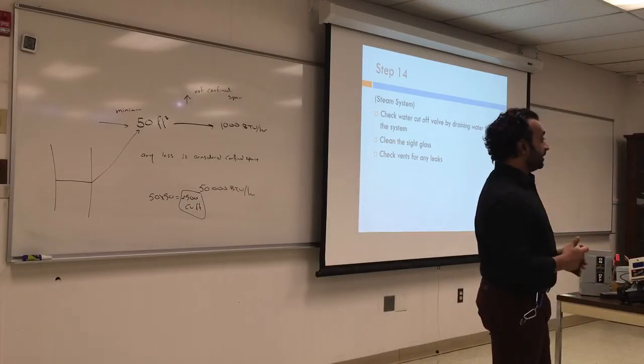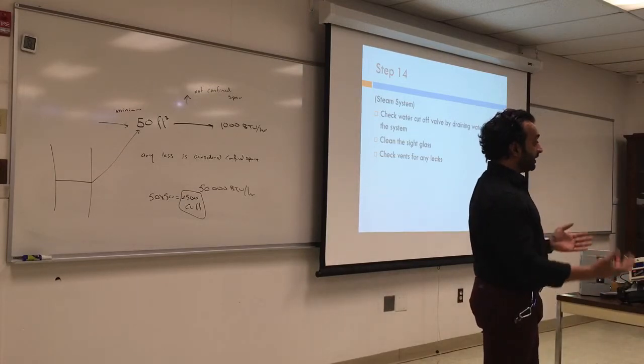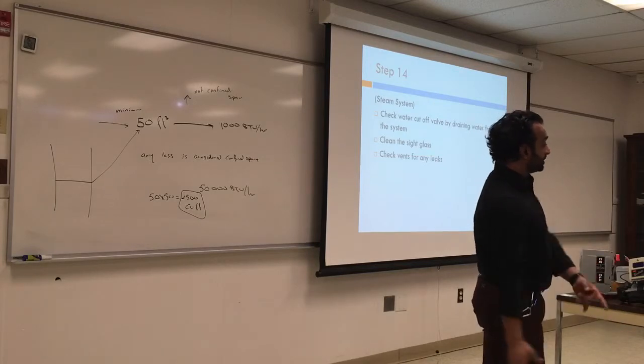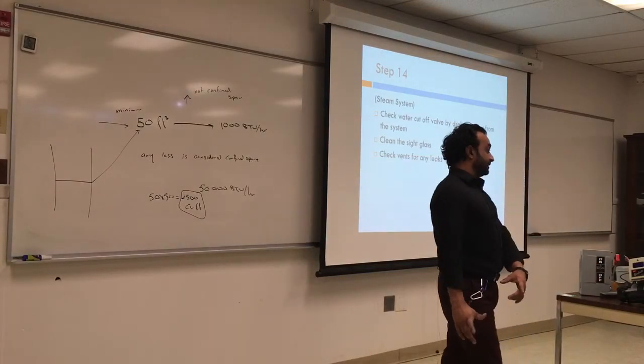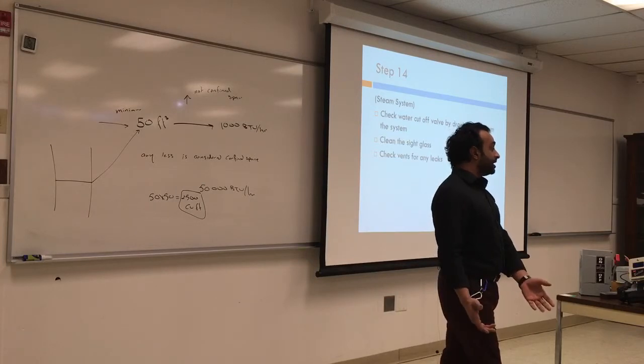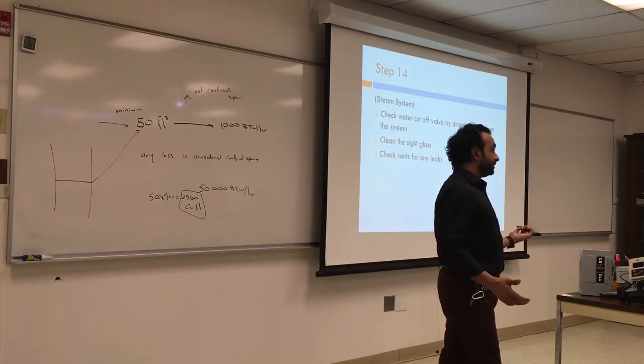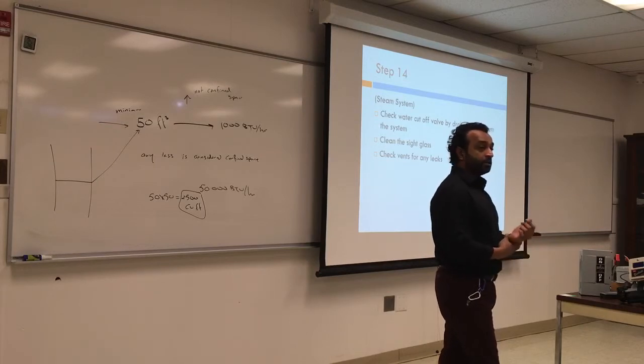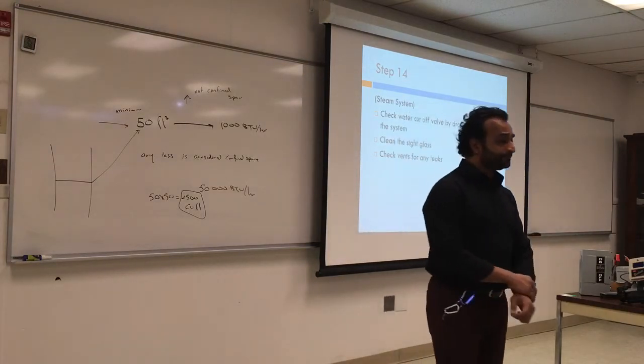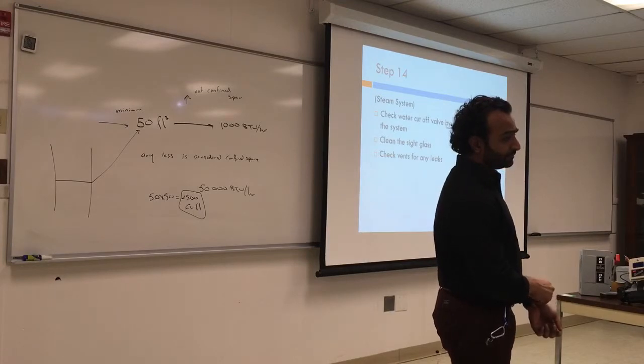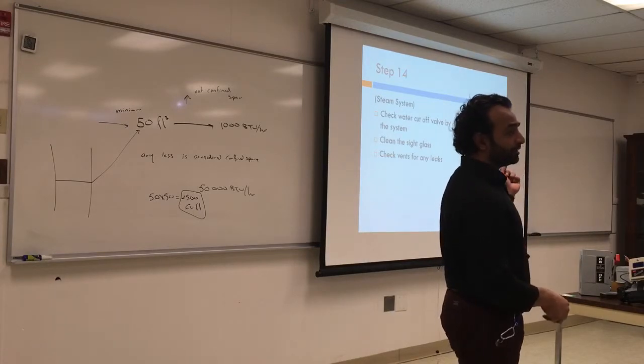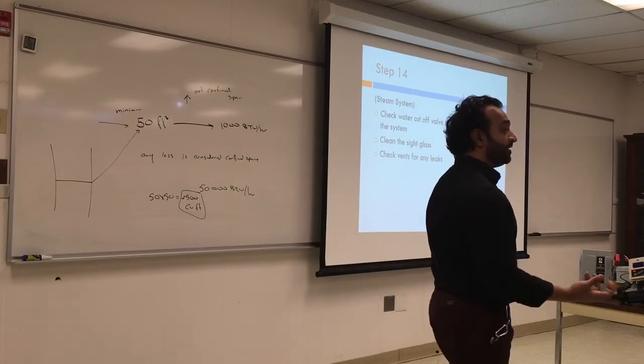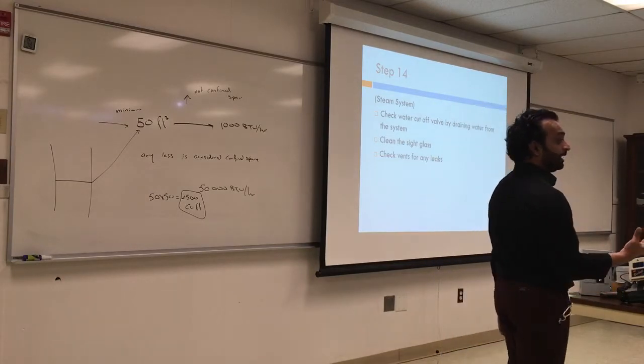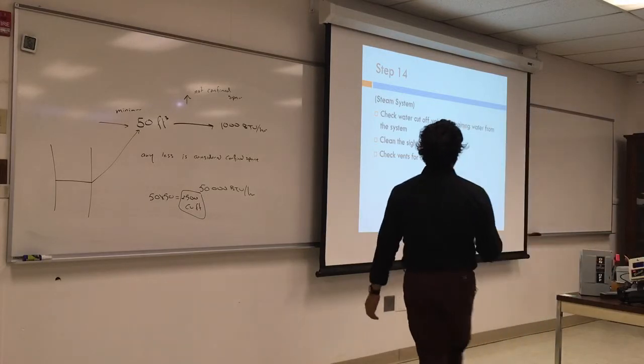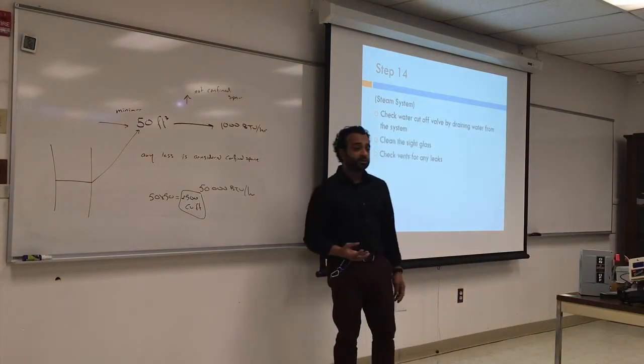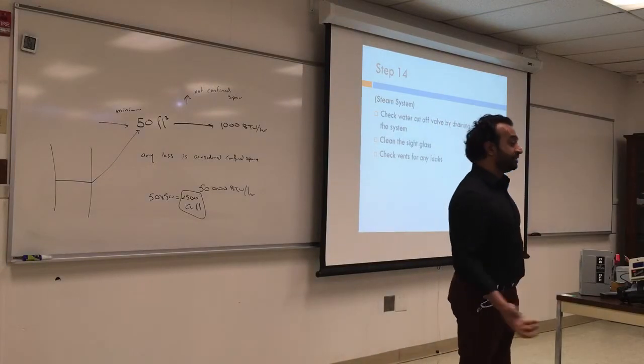Drain where? Every steam boiler has a drain at the bottom. Usually there's a hose and there's a small drain in the basement. It's not that big a bucket. It shouldn't be more than 6 gallons inside the boiler. So drain the system. And it's a good idea to flush the system once a year. So once you drain that, then you'll notice the sight glass start draining as well. And then you see also that it will cut off. And if you have an advanced low water cutoff, it will light up telling that there is low water. So always check for the water system. For hot water system and for steam system, it's very essential that you drain the system.